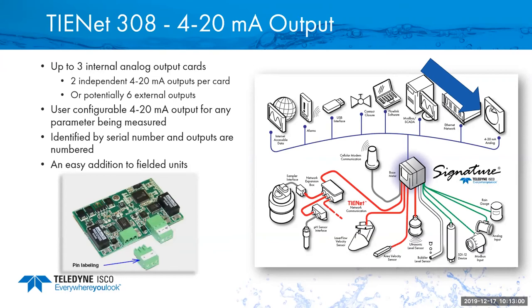The TIENet 308 analog output card is used to take a 4 to 20 signal out of the signature into, say, a SCADA system, PLC, or maybe a chart recorder or whatever else you may want to bring the 4 to 20 out of the signature. There are two channels on each one of these cards that we've talked about, meaning you could do a 4 to 20 out for level or a 4 to 20 out for flow or pH or something like that. On each card, you could do 2 outputs, and it doesn't matter which parameter it is, you can mix and match.